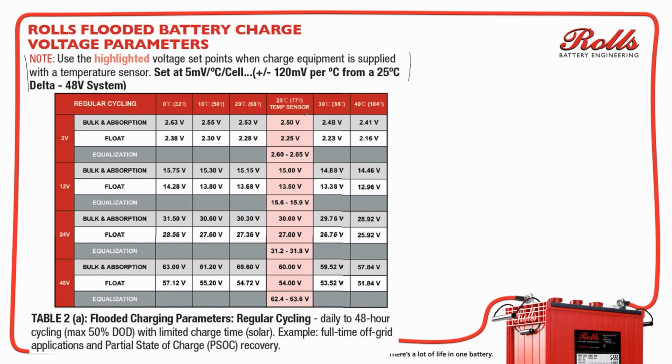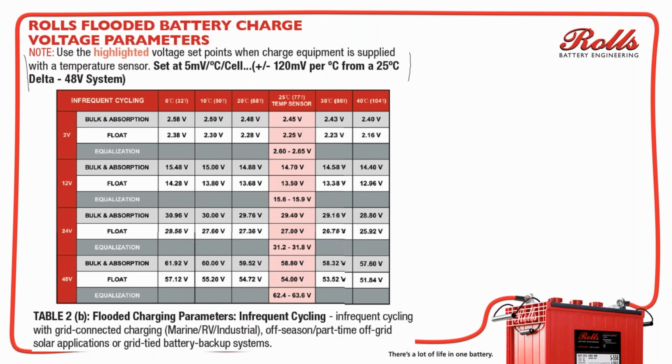So what you do is you install a system with the battery temp sensor and you program the system. There are two charts: this chart and the next chart, which is for lightly loaded systems. So this is the second chart for lightly loaded systems, okay? For flooded lead acid batteries, your bulk and absorption voltage should be between 2.45 and 2.5 volts per cell at 25 degrees C.